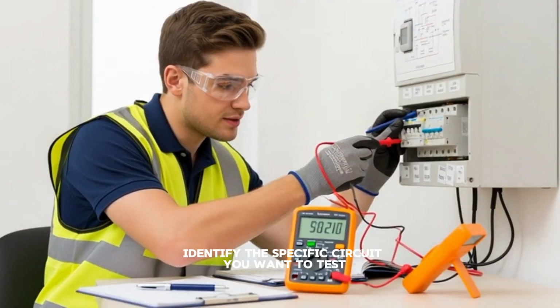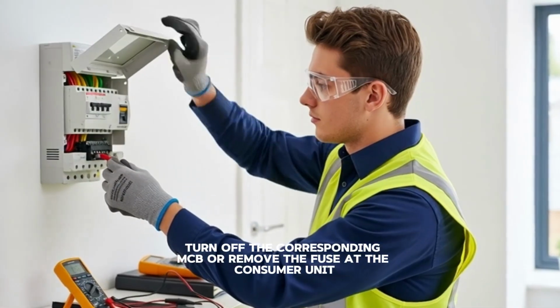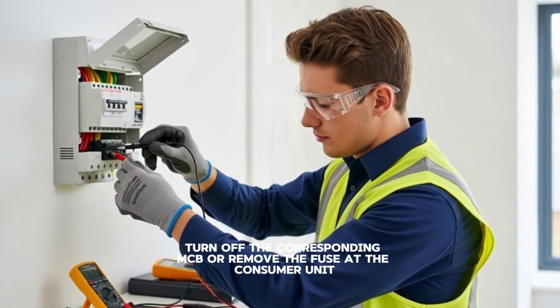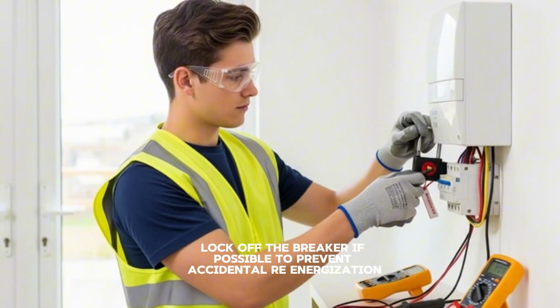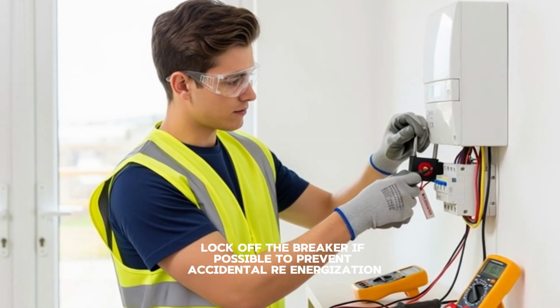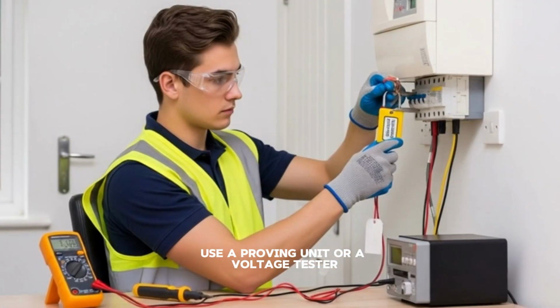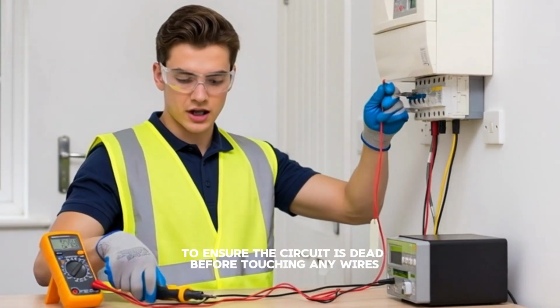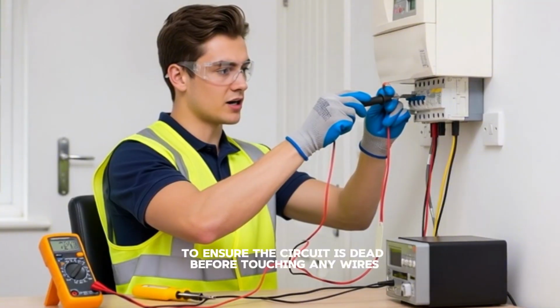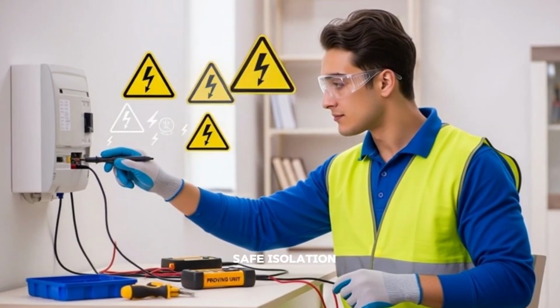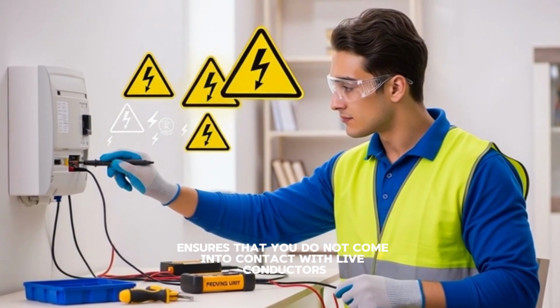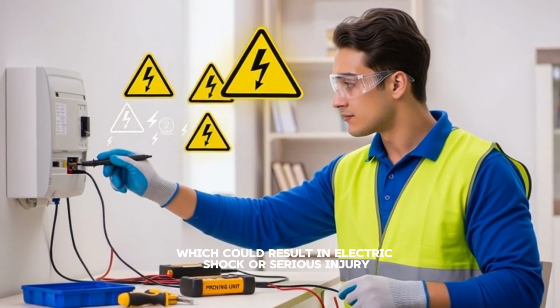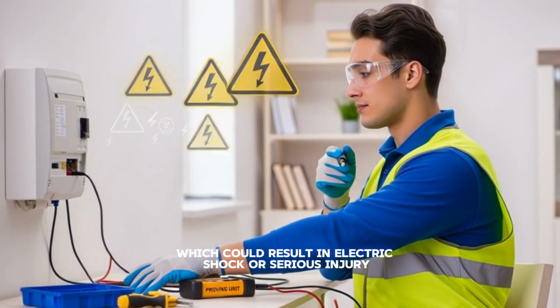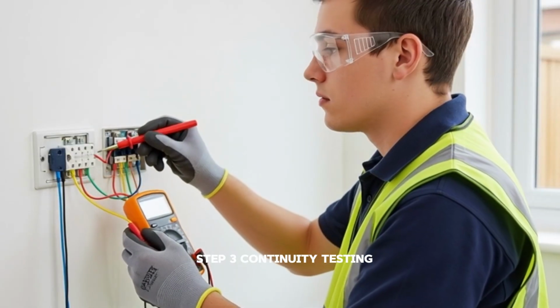Identify the specific circuit you want to test. Turn off the corresponding MCB or remove the fuse at the consumer unit. Lock off the breaker if possible to prevent accidental re-energization. Use a proving unit or a voltage tester to ensure the circuit is dead before touching any wires. Safe isolation ensures that you do not come into contact with live conductors, which could result in electric shock or serious injury.